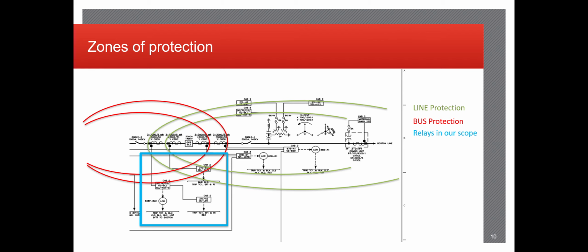We're going to identify the relays in our scope. Those will be our line relays down there. We're going to assume that they're going to be replaced, and it'll be our job to take care of the isolation and restoration of the relay circuits, testing the relays themselves, and identifying them to be the correct ones per the design intent.